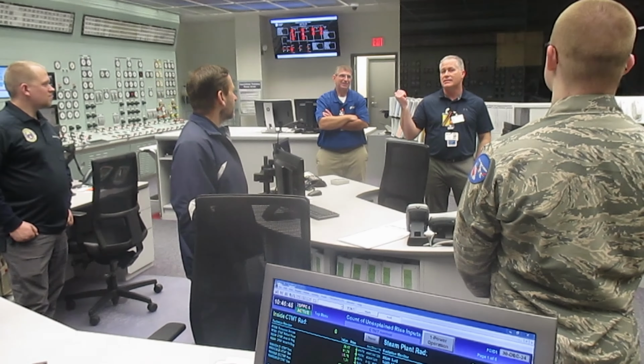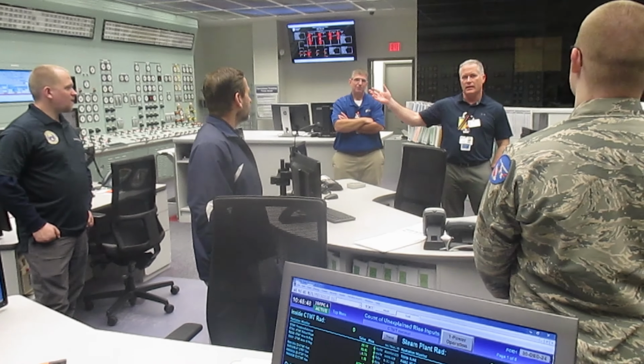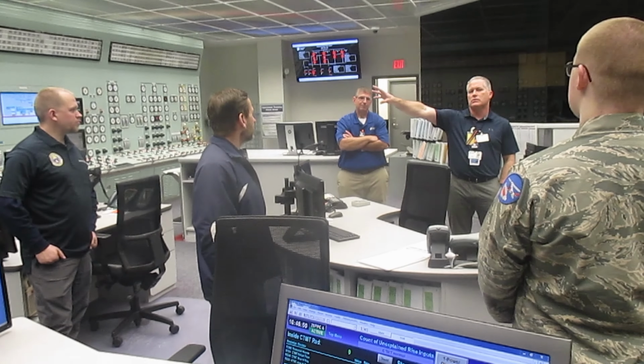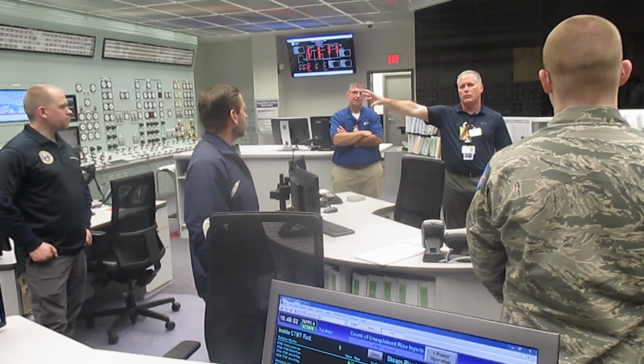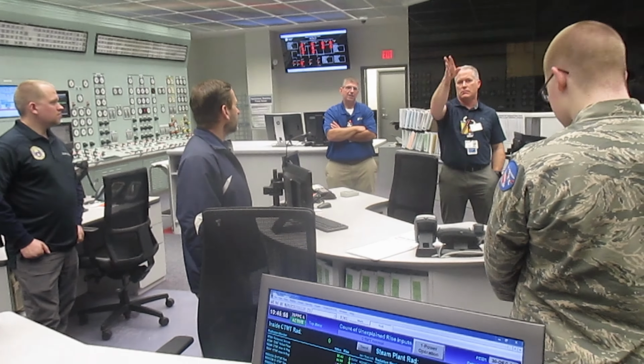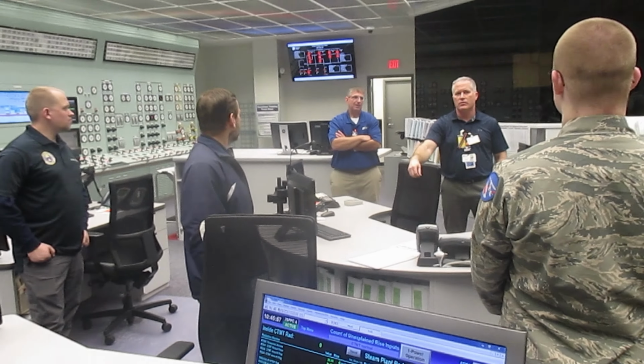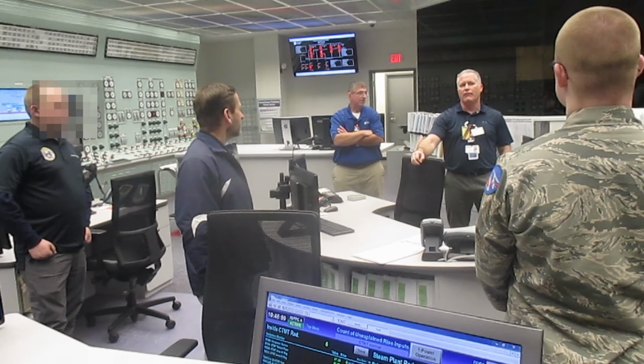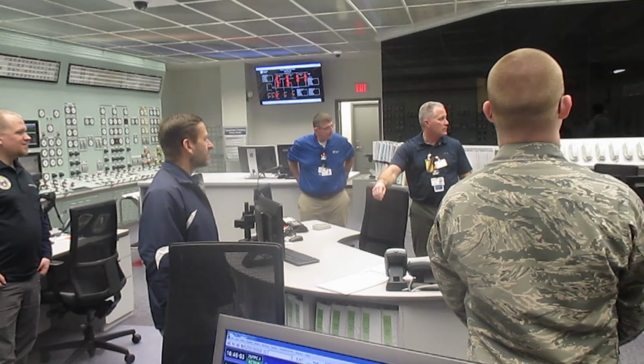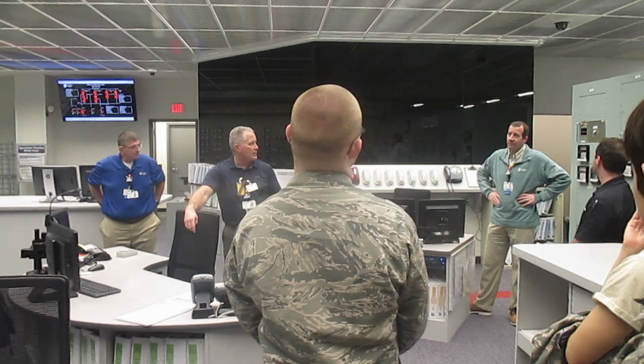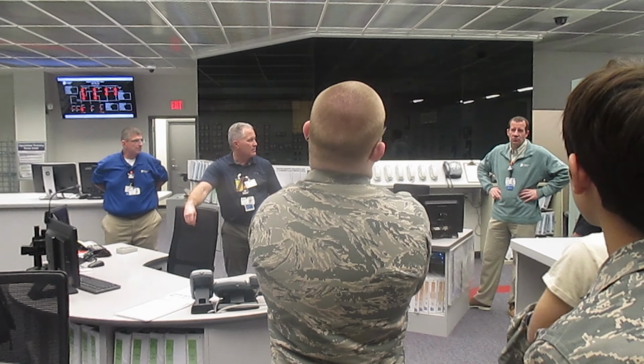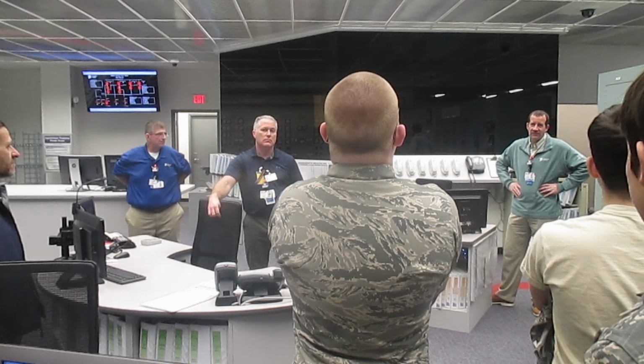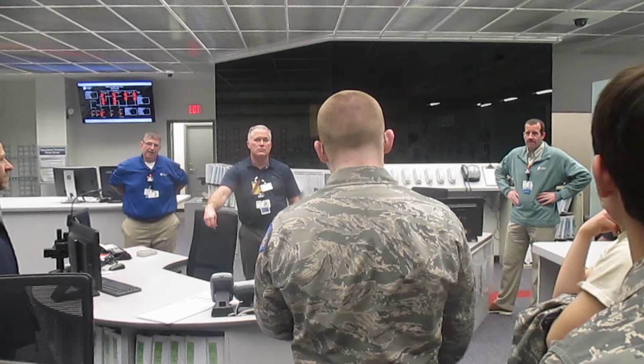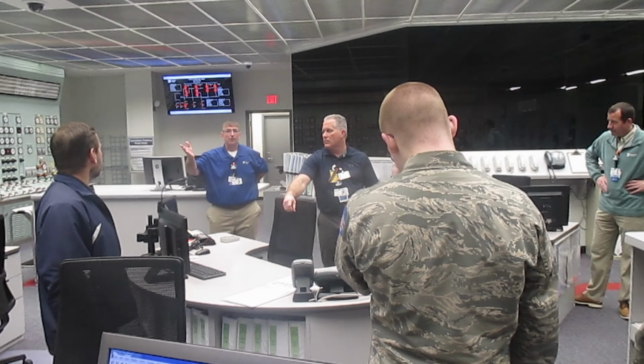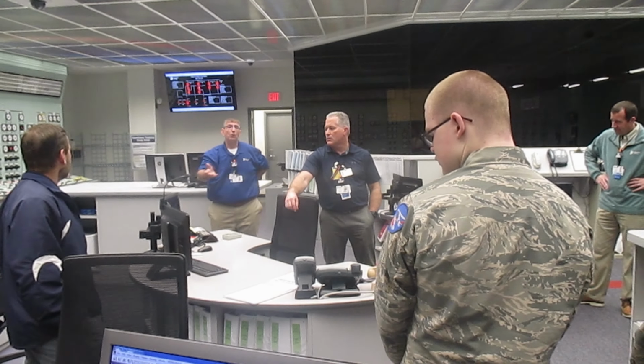So we don't have a cooling tower. Long Island Sound is what we use. We pull in seawater to go through those condensers to cool the steam coming through the turbine, and then it's discharged out the other side. With both units online at full power, we heat the incoming water about 18 to 20 degrees, so it comes in at 50 degrees and goes out at 70 degrees. The reason we can do that is because the temperature of the Long Island Sound is cool enough that we don't need a cooling tower.